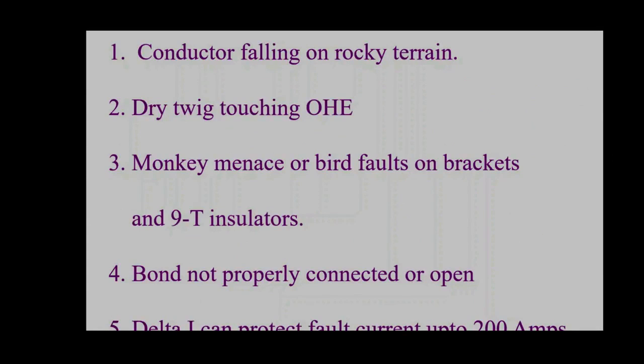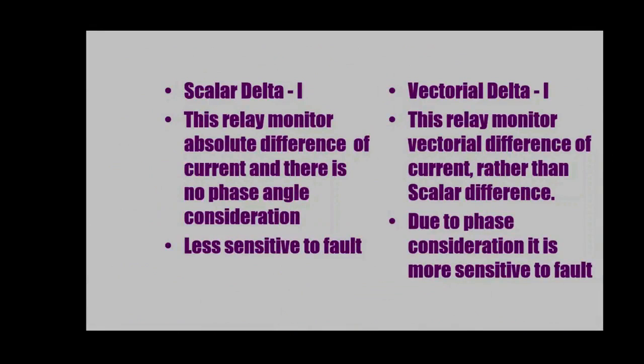Dry twig touching an overhead line. So, the railway being such a vast network, the overhead line will be passing through forest areas. So, some trees may touch the overhead line because of wind in unmonitored sections. A tree will be a very high resistance. That time, this will happen. Monkey or birds or insulator problems. So, a monkey is jumping on the transmission line and hanging, because of that the line gets cut. Open circuit, like bonds not connected or open. So delta I can protect fault current up to 200 amps. That's in primary. Two types as mentioned, scalar and vector, is also shown here.